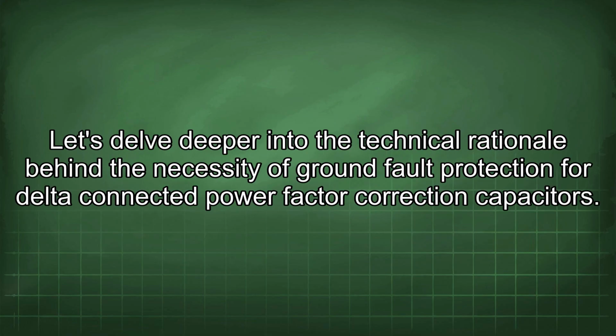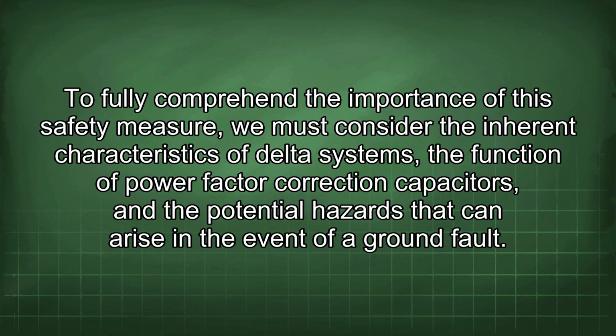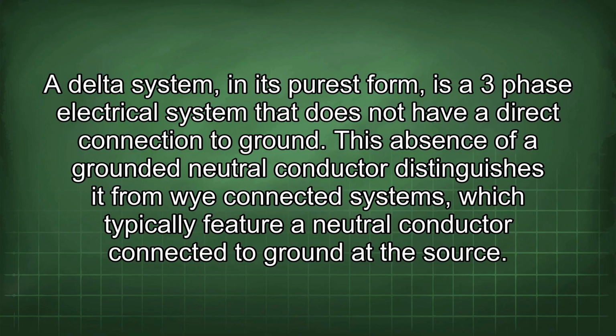Let's delve deeper into the technical rationale behind the necessity of ground fault protection for delta-connected power factor correction capacitors. To fully comprehend the importance of this safety measure, we must consider the inherent characteristics of delta systems, the function of power factor correction capacitors, and the potential hazards that can arise in the event of a ground fault. A delta system, in its purest form, is a three-phase electrical system that does not have a direct connection to ground. This absence of a grounded neutral conductor distinguishes it from Y-connected systems, which typically feature a neutral conductor connected to ground at the source.